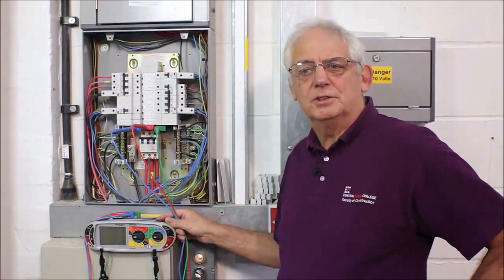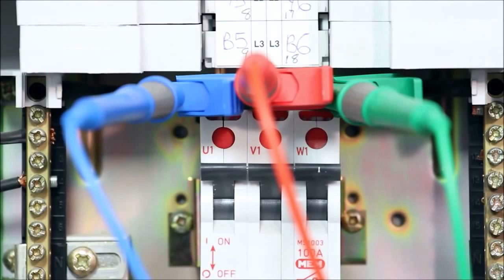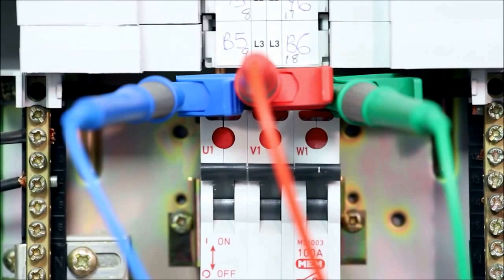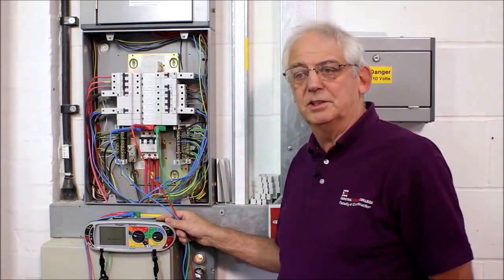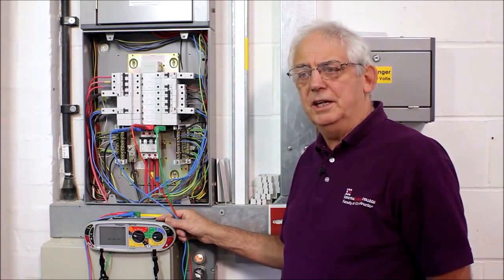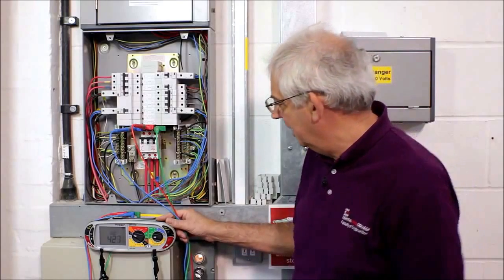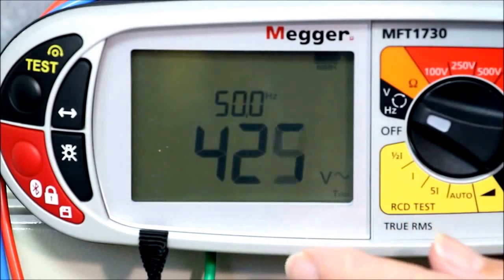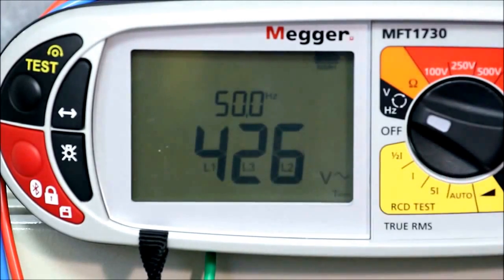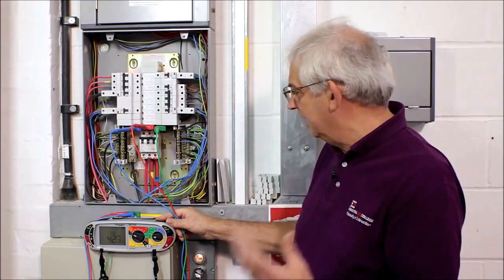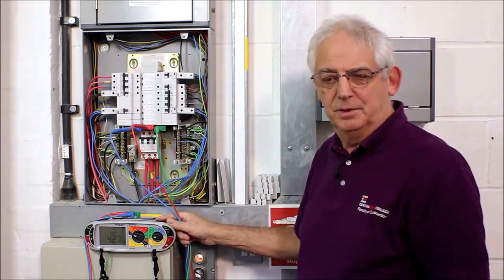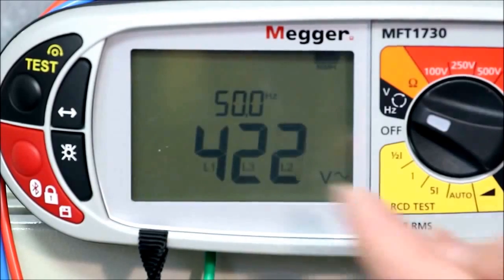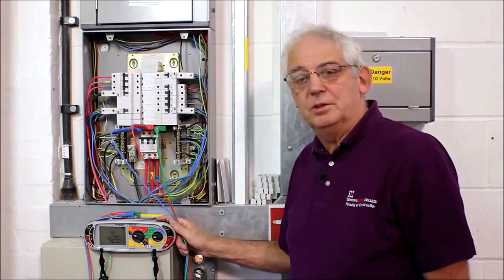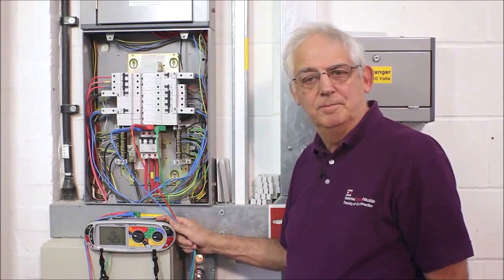And just for demonstration's sake, I've swapped the 2 leads over. We've now got blue, red and green rather than red, blue and green. If I turn it on to phase rotation again, we'll see that it will come up the wrong way around. And we've now got L1, L3 and L2. So you can see that it's flashing, which is indicating that there's something wrong. It's a warning, and it also comes up visually so that you can see that it is connected around the wrong way. So that's phase rotation.